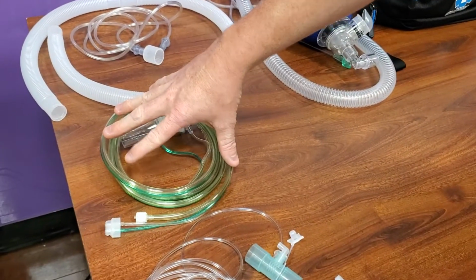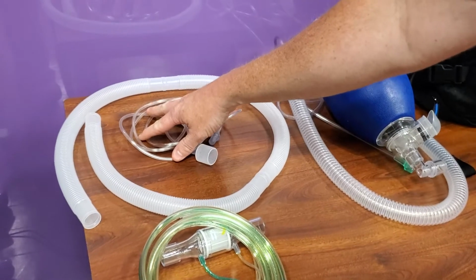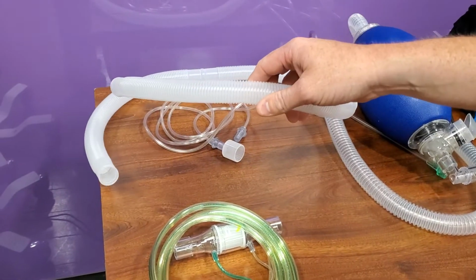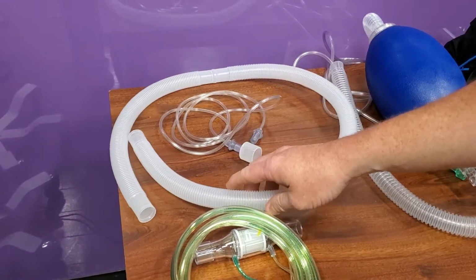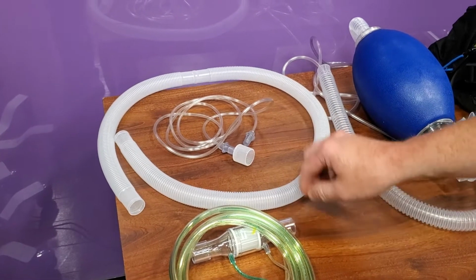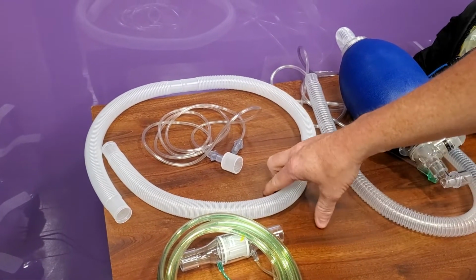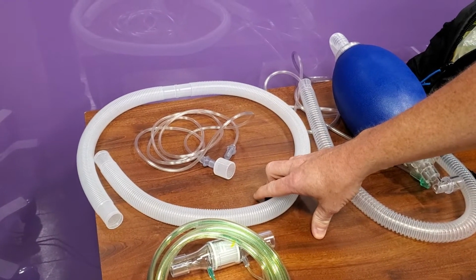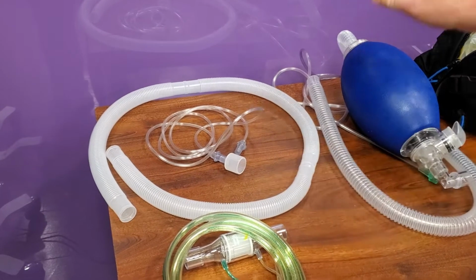Our injector module, our O2 tubing for our check, and then there's a 1 meter piece of tubing here that we use for the nitric check as well. It has to be this length and exact piece of tubing so that it gets an accurate count here, and then just a BVM for our test.